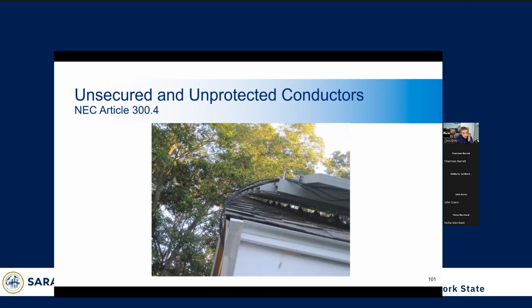These conductors in this image are not protected from physical damage. You can see it goes up over the racking system and over the sharp edge of the shingles. Eventually, these are going to fail. These conductors will be in contact with the roof, and they'll wear away until the copper is exposed, and then they'll fail, likely well before the 25 years that this should be designed for. And this contractor should have used conduit to protect these conductors going around the edge of that.